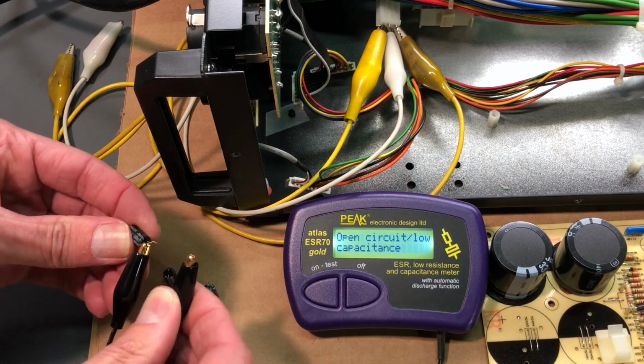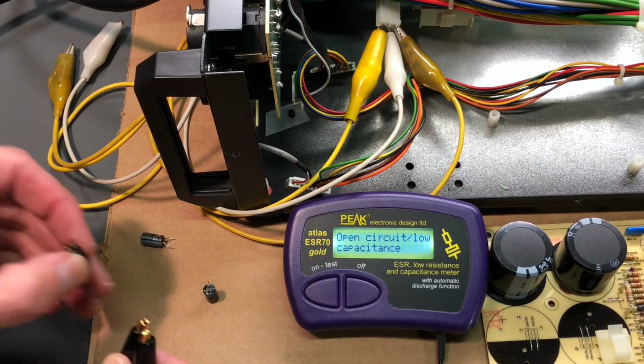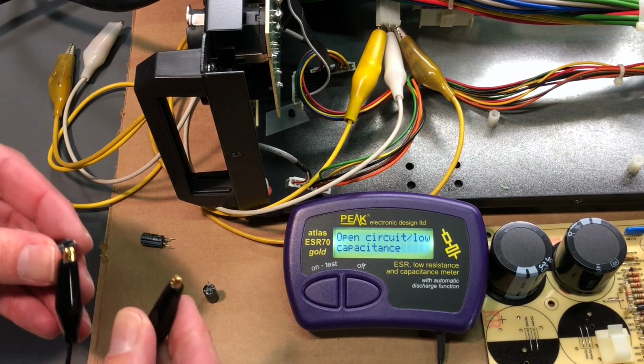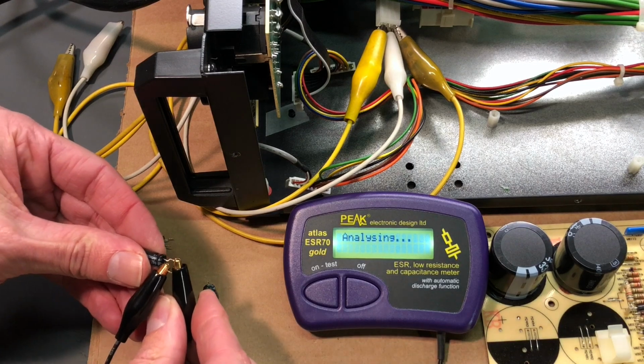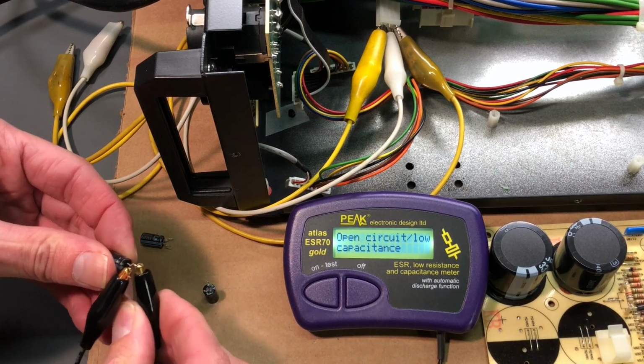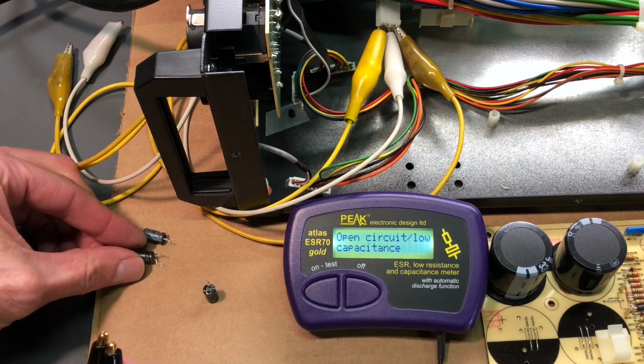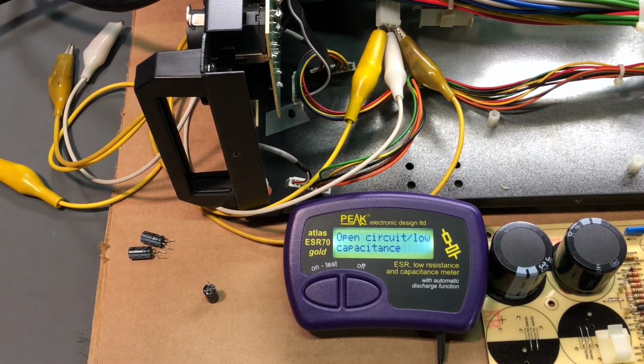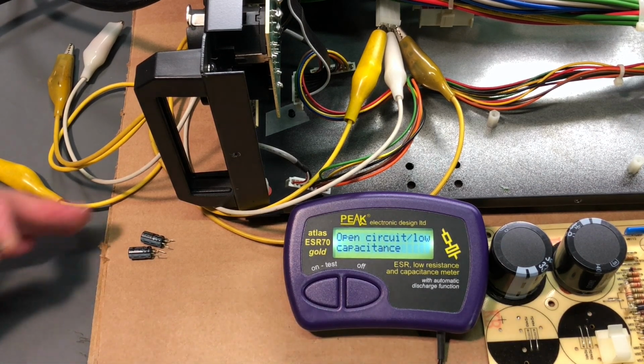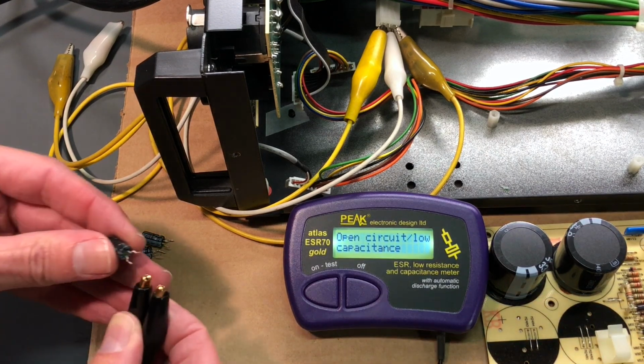Wow, that one's definitely faulty, no question about that. That one's also faulty, so that would certainly explain why those relays were chattering. I think that protection mode was happening because the turn-on delay wasn't working right, and it was just keeping it in the protection mode. If it's working correctly, the protection mode indicator lights will turn on briefly at power up while the delay is occurring, and then should turn back off. We'll see if that actually happens, but no question those are definitely defective.